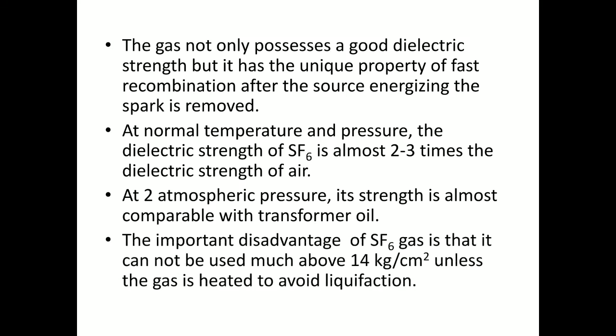But there is one major disadvantage associated with SF6 gas: at normal temperature and pressure, the nature of SF6 gas is vapor. But as the pressure increases, if it goes beyond 14 kg per centimeter square, the nature of the gas will change from vapor to liquid. So we need to be very careful while using SF6 gas as an insulating material in electrical equipment.